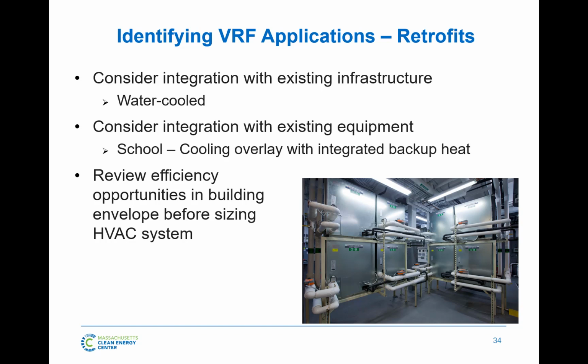Water-cooled works great when you might be doing a renovation of a building or an existing building that already has a condenser water loop. So there were water source heat pumps there from years ago. There's already a cooling tower that's in good shape. There's already that condenser water loop infrastructure there. Integrating water-cooled VRF into that is a very good option. It might even help sway your first cost a little bit by taking advantage of how that system lays out and what you already have in the building.